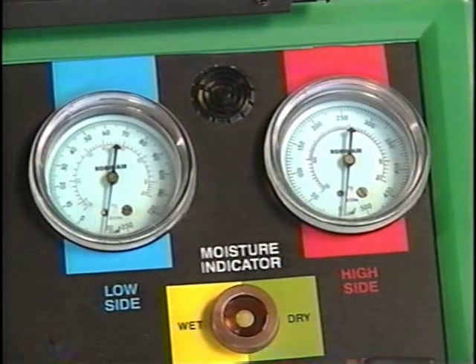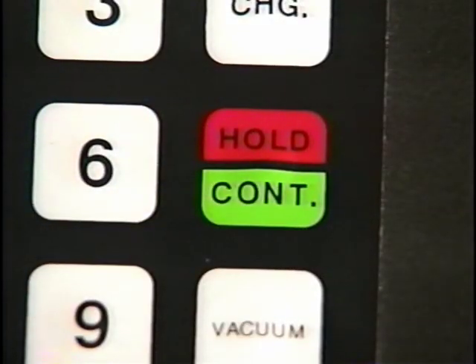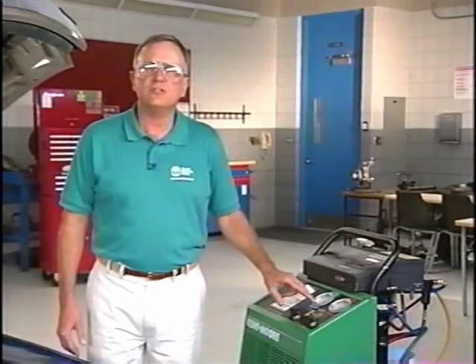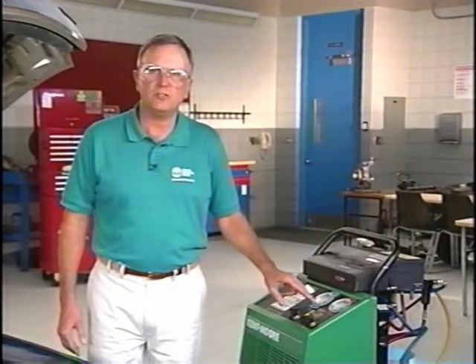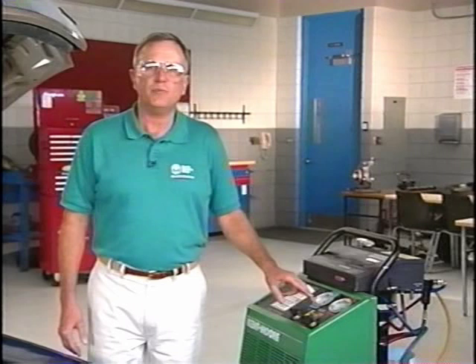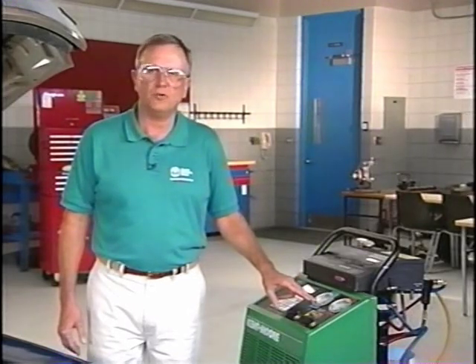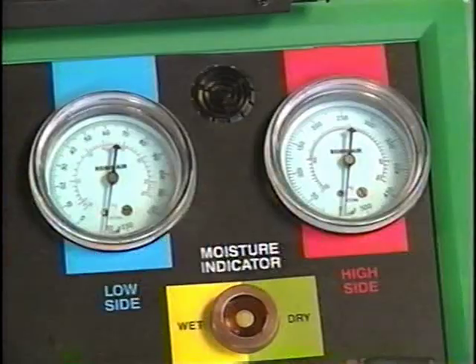You can use the control panel gauges to check for leaks during evacuation. After the vacuum pump has run for about 3 minutes or more, press the Hold Continue key and read the low side pressure gauge. A reading of 0 on the low side gauge indicates a major leak in the system. The repair has to be made before we can continue on with the evacuation process. If 27 to 30 inches of vacuum is indicated, close the low and high side valves and observe the gauges to see if the vacuum holds for a few minutes.